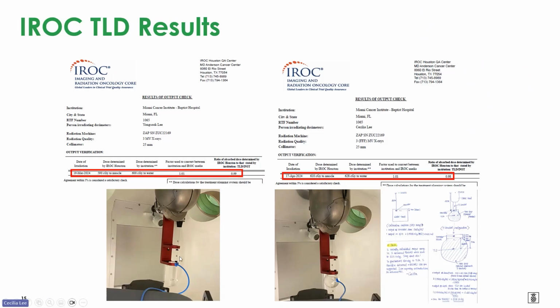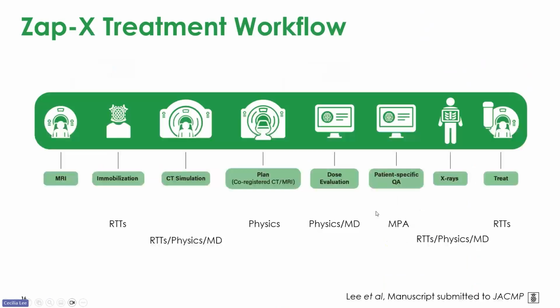We used 2 different setups. On the left, this was a SAD setup at dmax, and on the right, we used a different phantom. Both are provided by vendors. The geometry was not a SAD setup at dmax, so I had to calculate how much MU I had to deliver, but output was pretty good, within 1%, 2%.